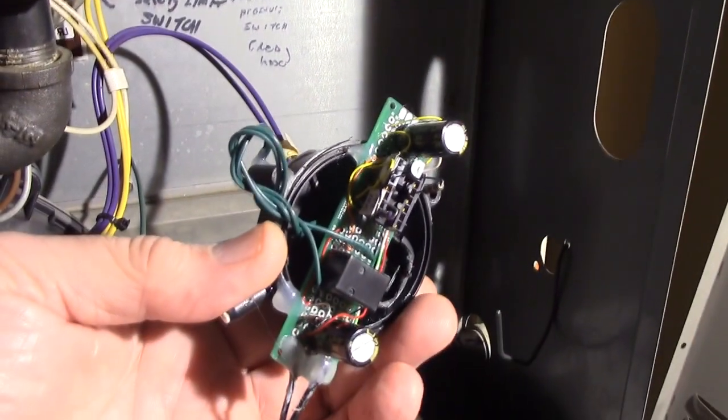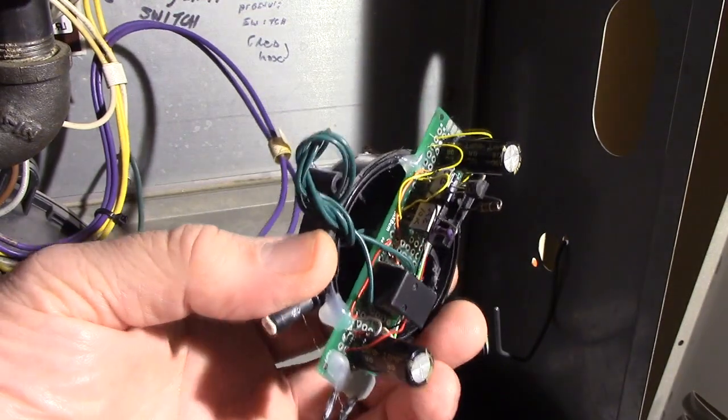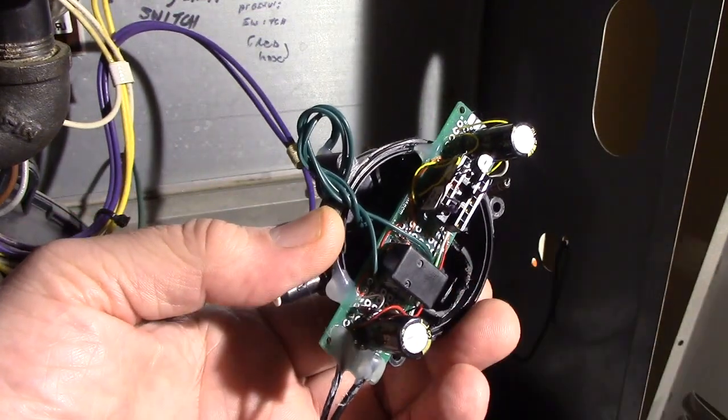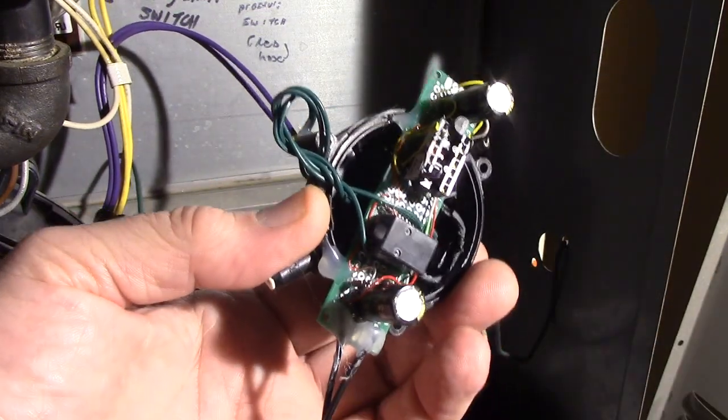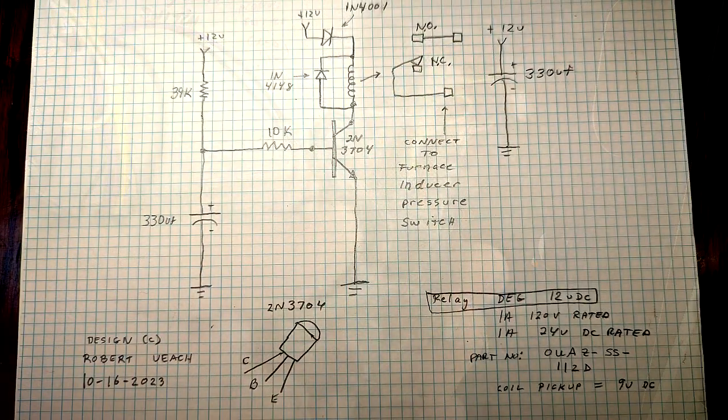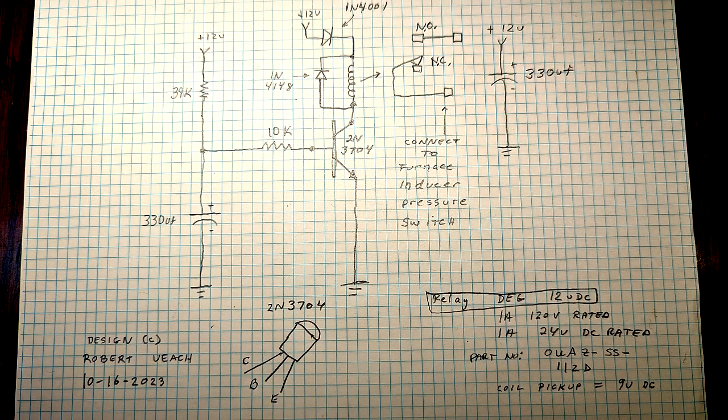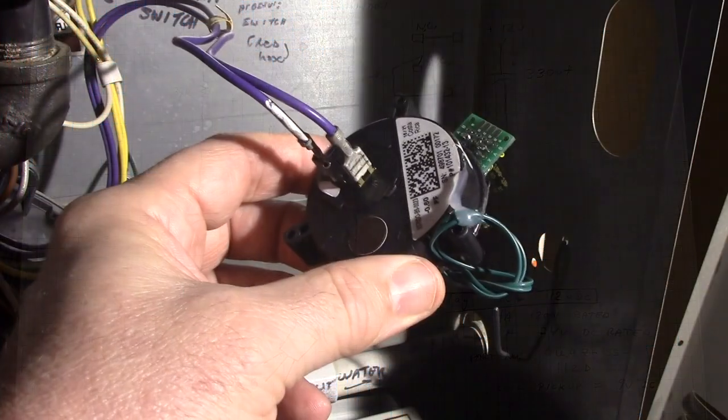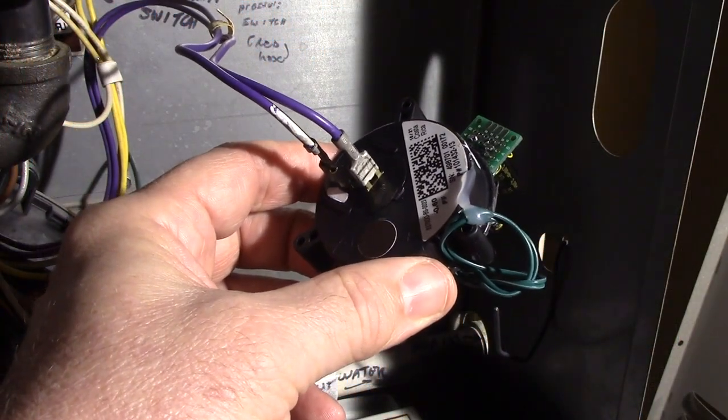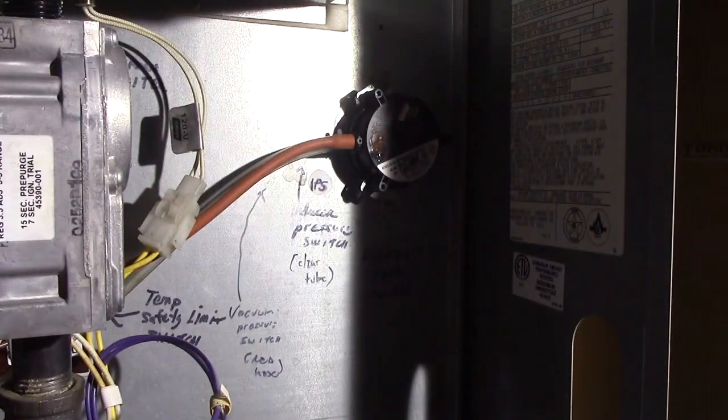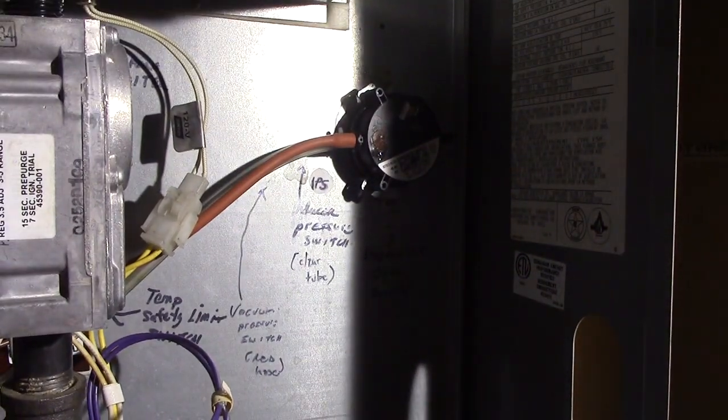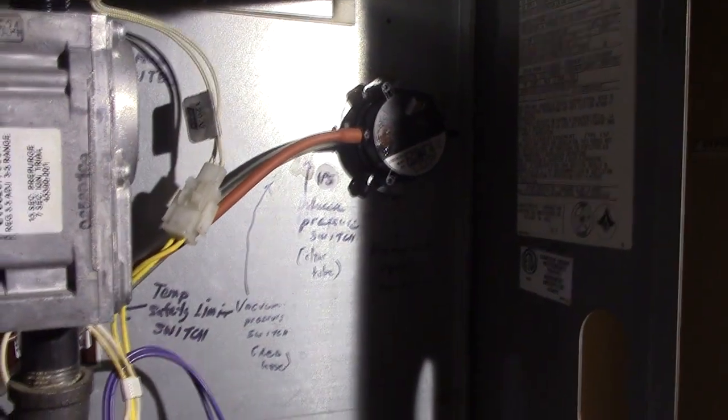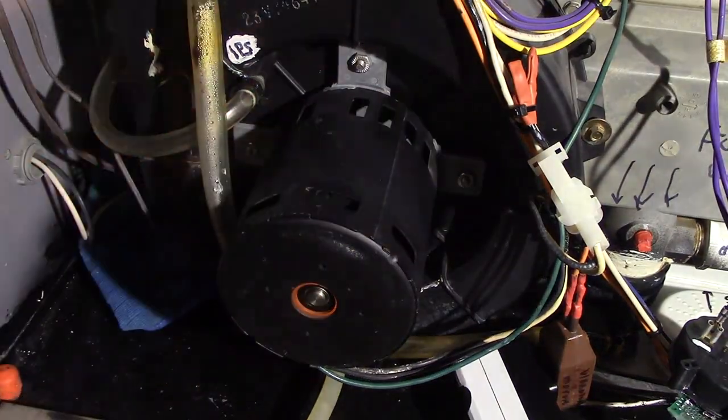I'm doing this to test the concept and it's worked flawlessly. I'm gonna have a schematic of this, but keep in mind this is a temporary fix - this is when you have your pressure switch failing and you don't have another one on hand. This is not something to permanently bypass because the pressure switch is very safe.